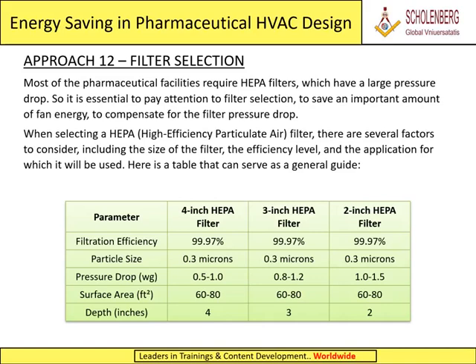Approach 12, Filter Selection. Most of the pharmaceutical facilities require HEPA filters, which have a large pressure drop. So it is essential to pay attention to filter selection, to save an important amount of fan energy, to compensate for the filter pressure drop. When selecting a HEPA, high-efficiency particulate air, filter, there are several factors to consider, including the size of the filter, the efficiency level, and the application for which it will be used. Here is a table that can serve as a general guide.